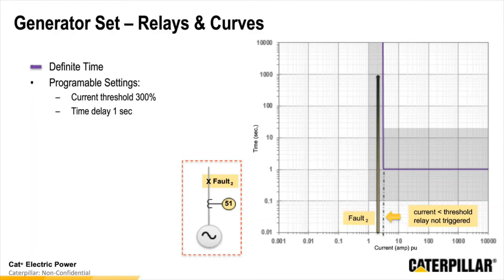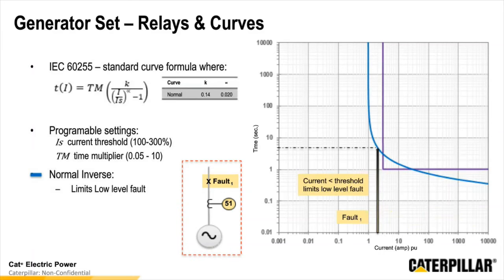So now if we were to have a fault within the system and the fault required just 200% current, and so we did not have a 300% over current, then we would end up providing that 200% on a continuous basis because the definite time trigger isn't able to actually identify that there was a failure because we set the current limit to 300%. So because of this, we don't only just use the definite time settings. It is our first setting, but not the only one we use.